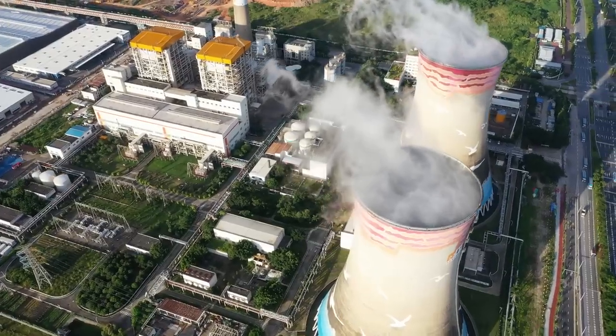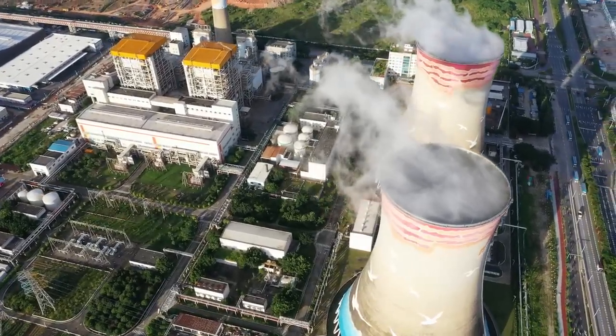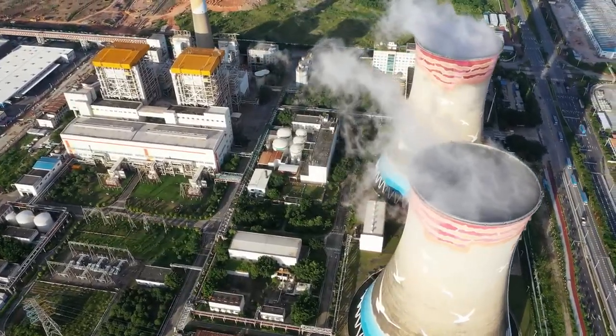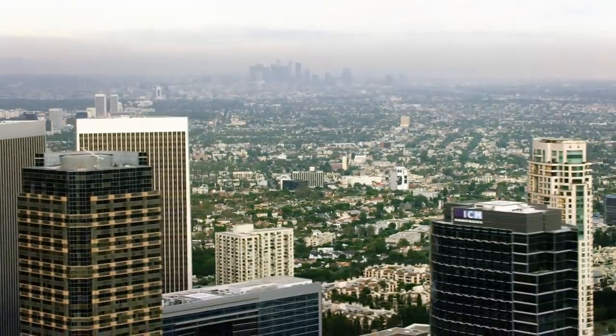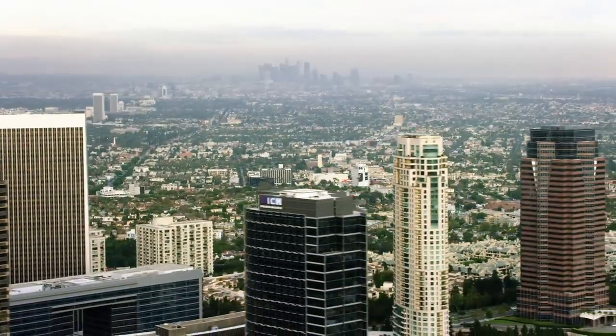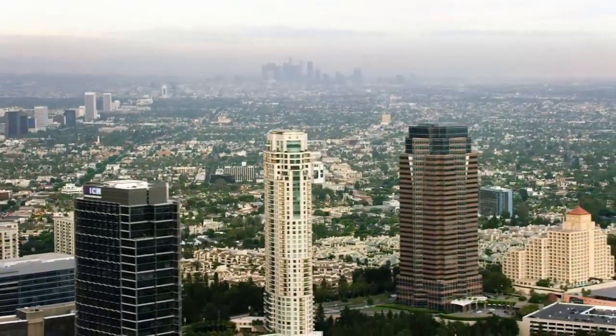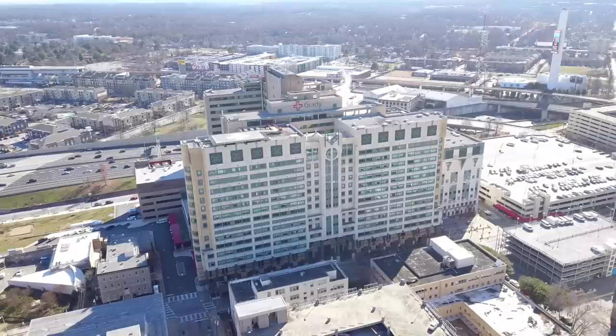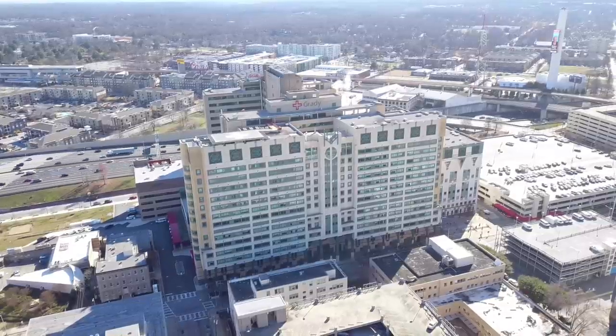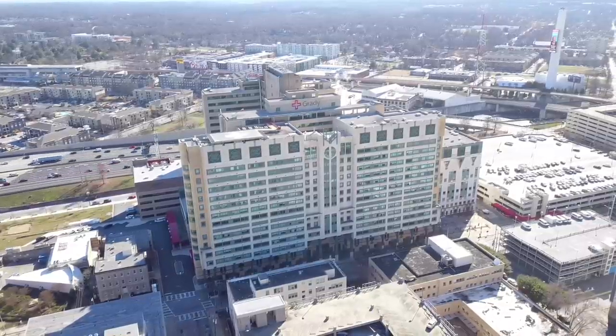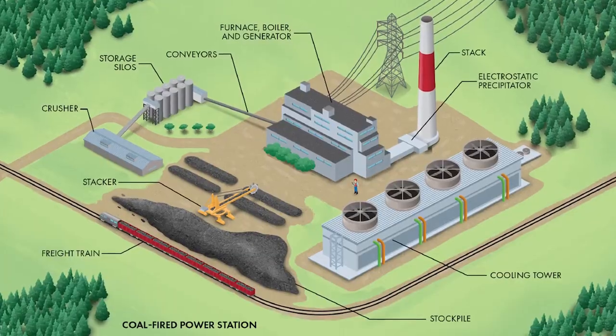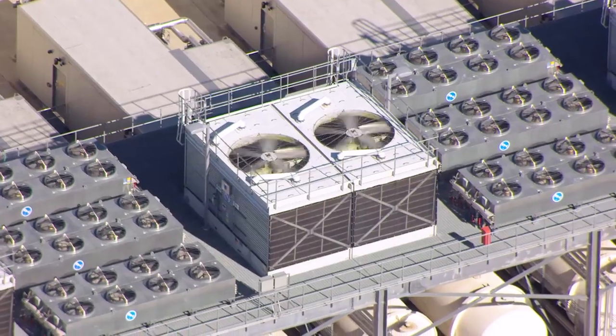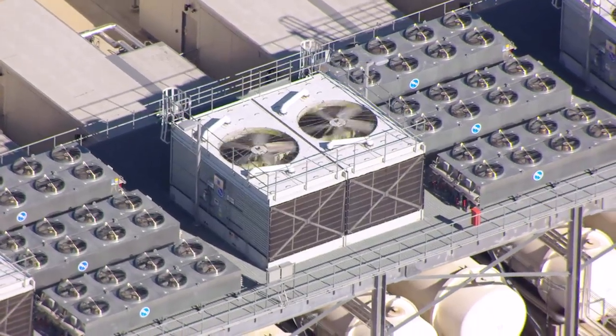But that definitely doesn't mean this is the only kind of cooling tower. In fact, hyperboloid natural draft towers are actually pretty rare, in the same way that thermal power plants are pretty rare compared to large office buildings, hospitals, and schools that often use cooling towers as part of the HVAC system. Those towers often use mechanical draft systems, basically using fans to create airflow instead of tall stacks. I talk a little bit more about this in my book. We still call them cooling towers, even though they usually aren't too towery.